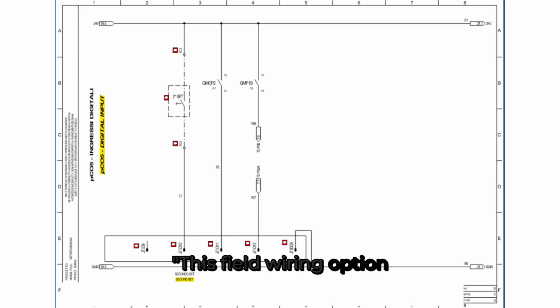This field wiring option allows the user to toggle between two operating set points. For example, a normal mode cooling set point and an energy-saving mode, or comfort and night operation set point. Next, we have the QMCP2 feedback, which is the compressor 2 circuit breaker signal. This input lets the controller confirm that the second compressor's breaker is switched on and that the protection circuit is intact. The third column represents QMF1B, which is the fan circuit breaker for the second fan motor.